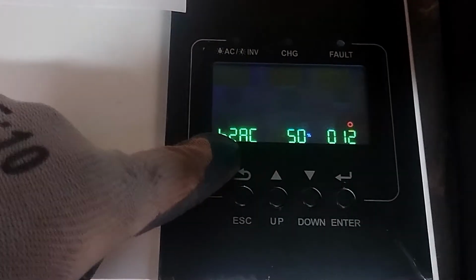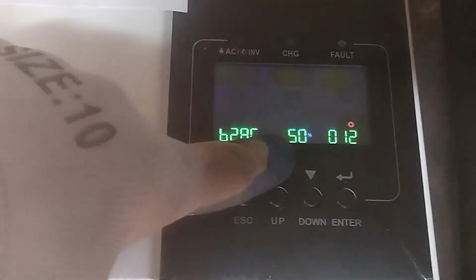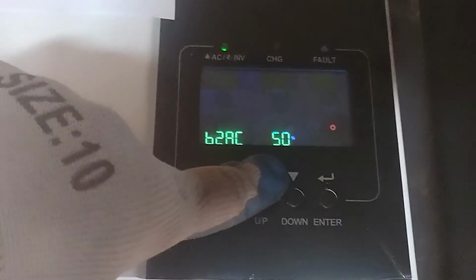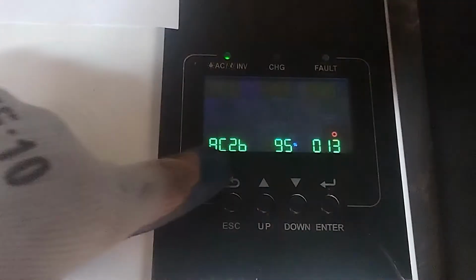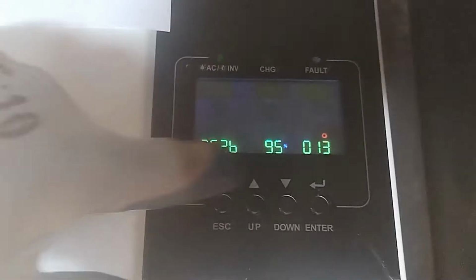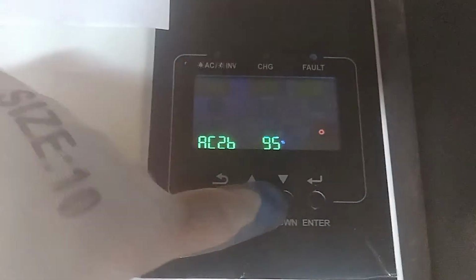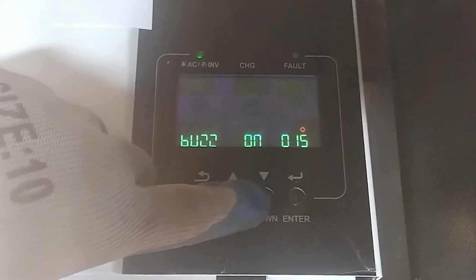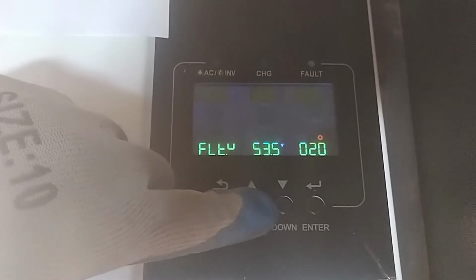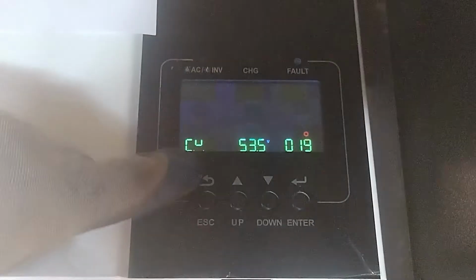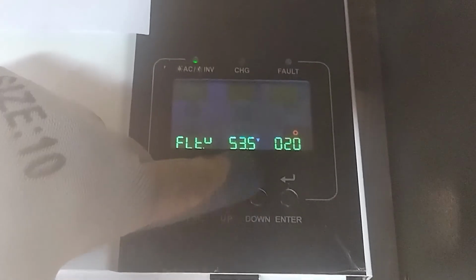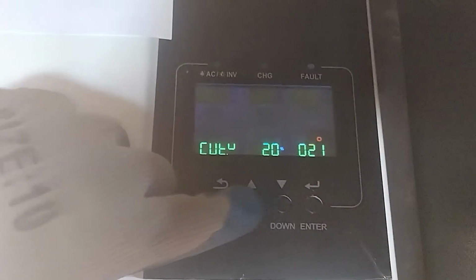So here is the battery going back to AC, which is to charge when it gets to 50%. It goes back to battery, cutting from grid back to battery, when it is at 95%. And the only charging source here is solar. So here we have the charging voltage CV being 53.5, with the floating voltage also at 53.5, and the cutoff at 20%.